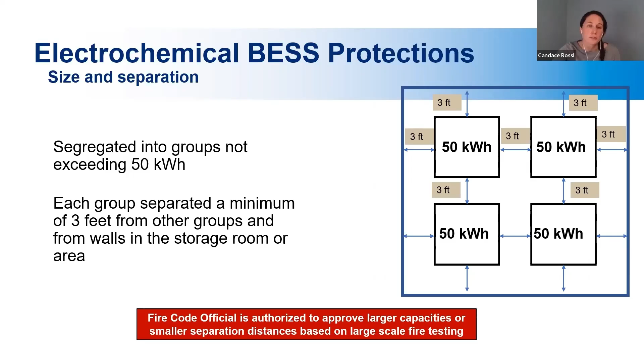So you'll see a lot of those storage container size projects that can basically be approved if the fire code allows those systems to be closer together. I think I have an image later in the presentation where you can actually see what one looks like on the inside, so we can get to that. But basically, this is part of the design of the system to make sure there's no propagation, or to avoid thermal runaway in a design kind of way. So for authorizing larger capacities, it needs to be shown in that large scale fire testing that there is not a risk in increasing those capacities or lowering those separation distances.